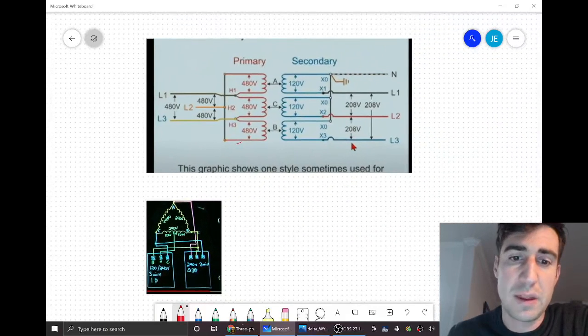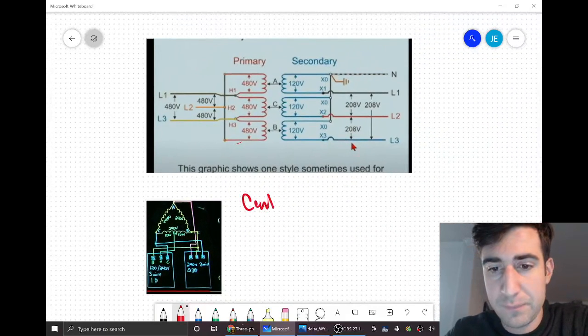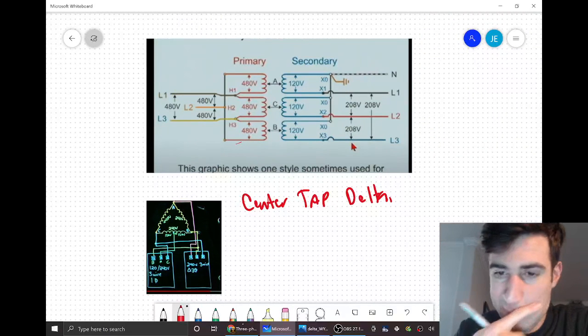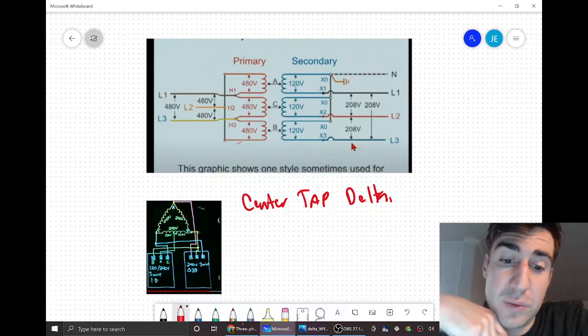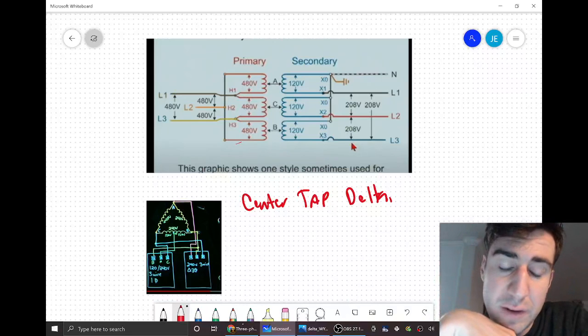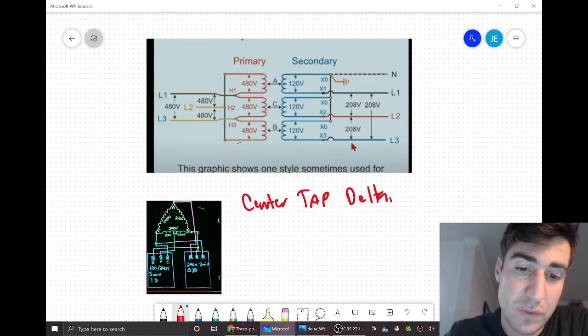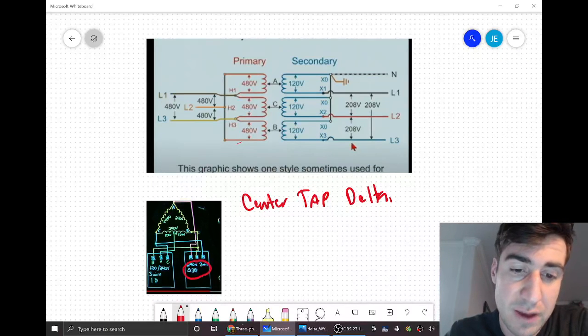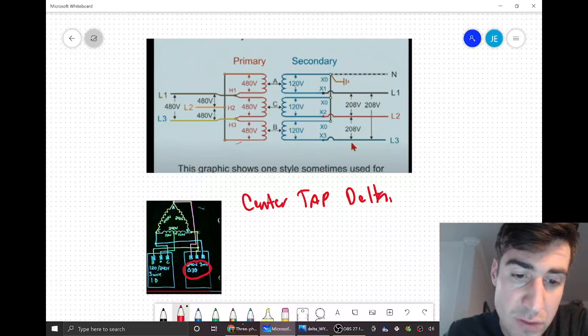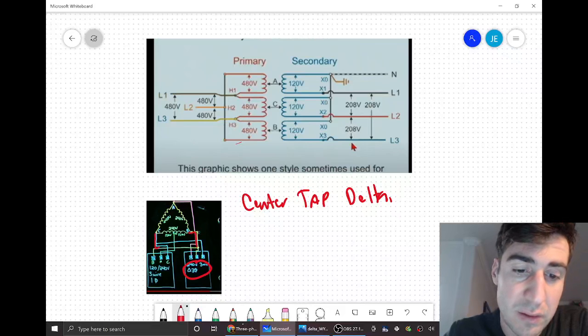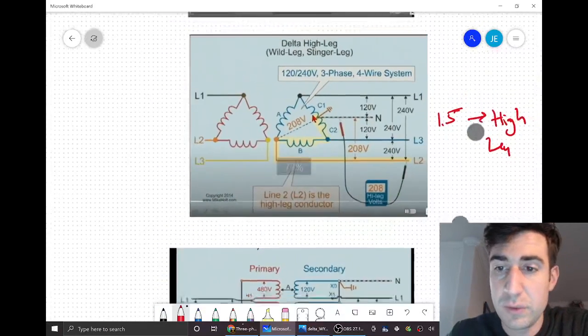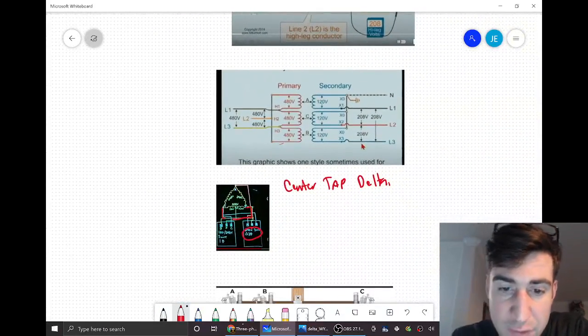Really quick, this is why we use the center tap delta. Center tap delta allows you on the distribution and the customer side of things to easily convert. You can draw 240 3-wire 3-phase, or you can choose, using the 2 non-high wires and the neutral, to have 120/240 3-wire.